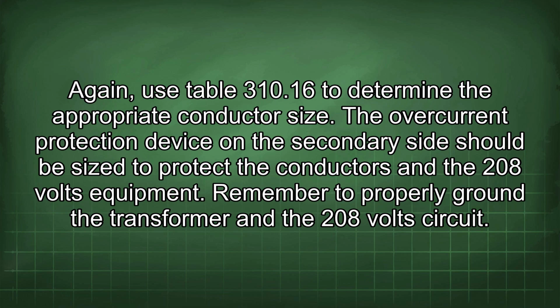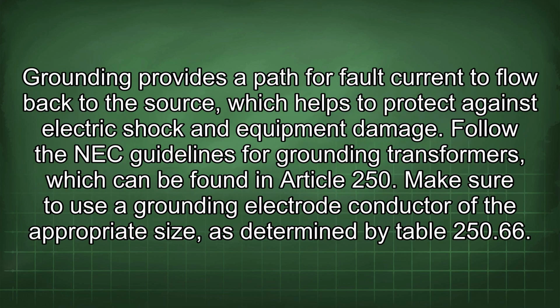The overcurrent protection device on the secondary side should be sized to protect the conductors and the 208 volt equipment. Remember to properly ground the transformer and the 208 volt circuit. Grounding provides a path for fault current to flow back to the source, which helps to protect against electric shock and equipment damage.